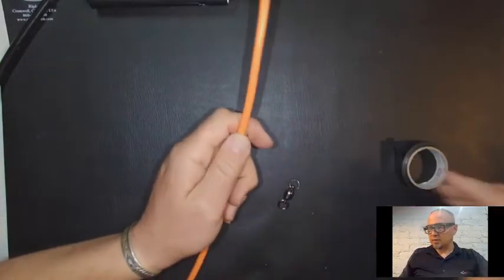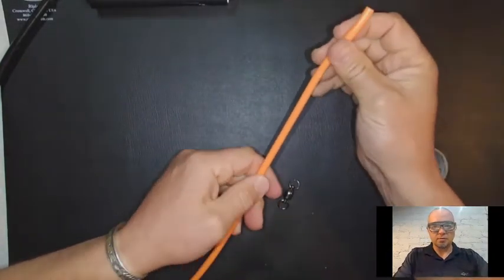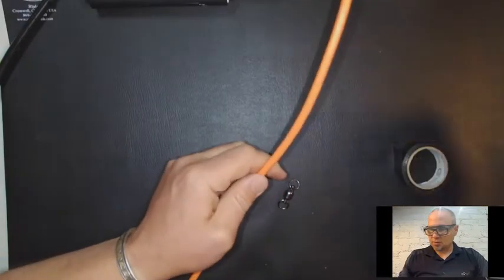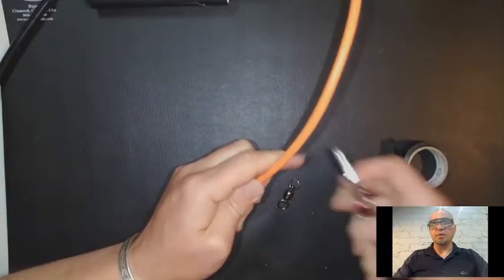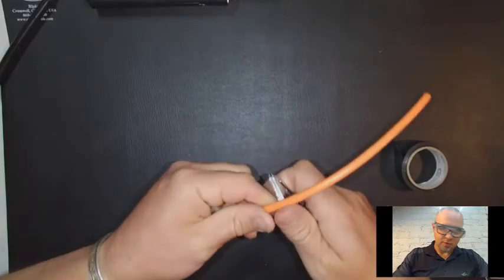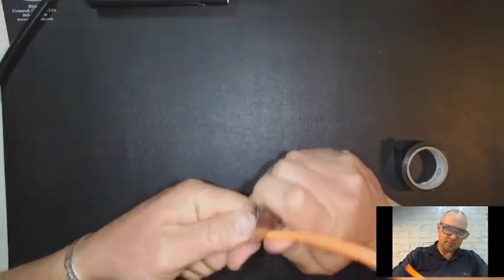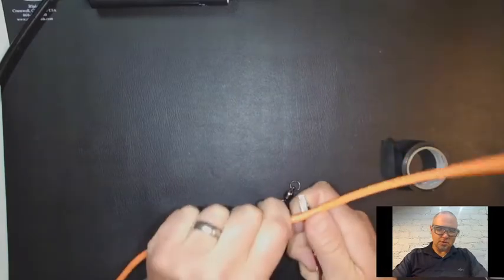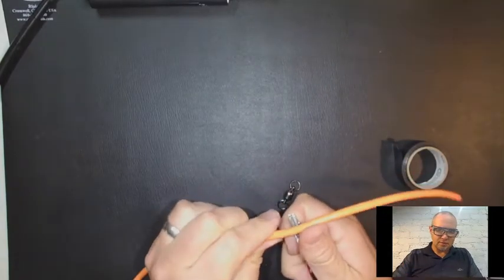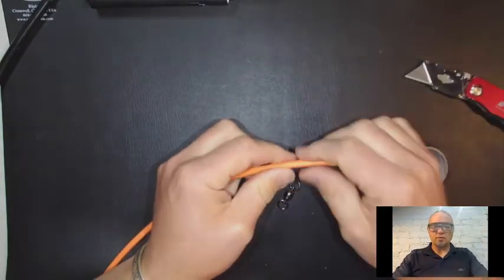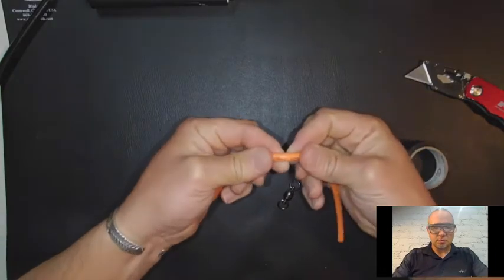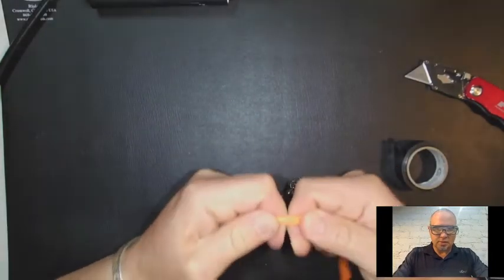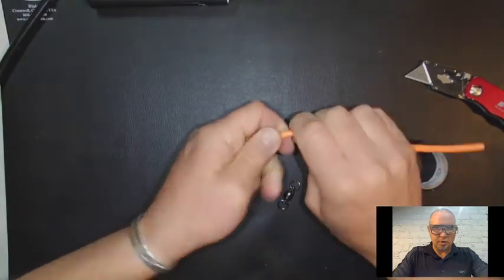So we're going to want to give ourselves probably about 8 to 12 inches to work with. And I'm going to pull off the jacket. I want to just score just enough. I don't want to cut all the way through the jacket, but I can just bend the jacket a little bit and it can pull apart.